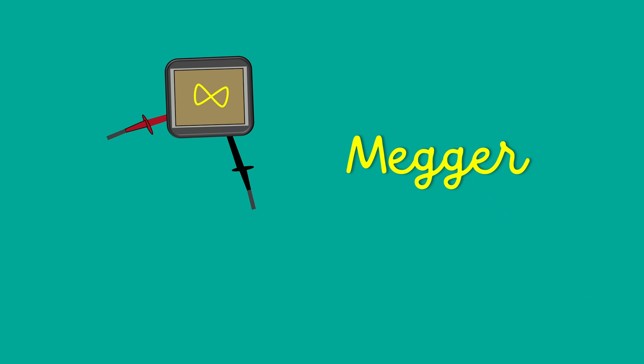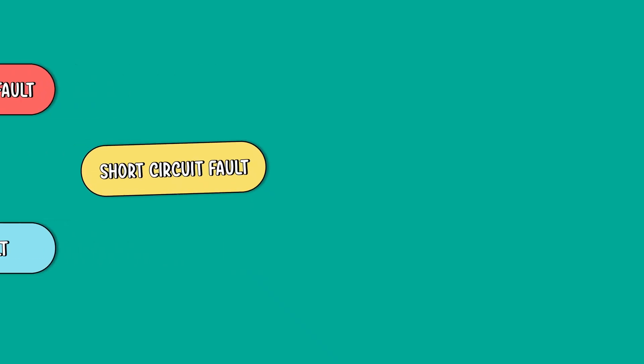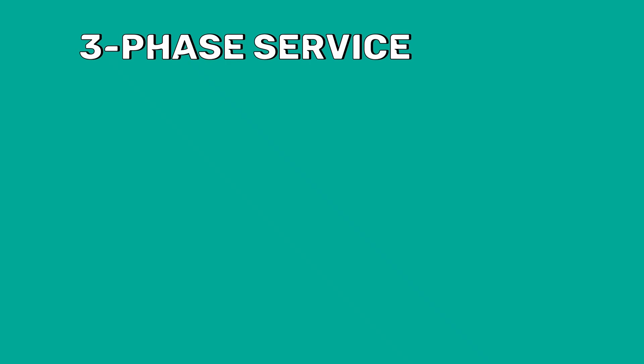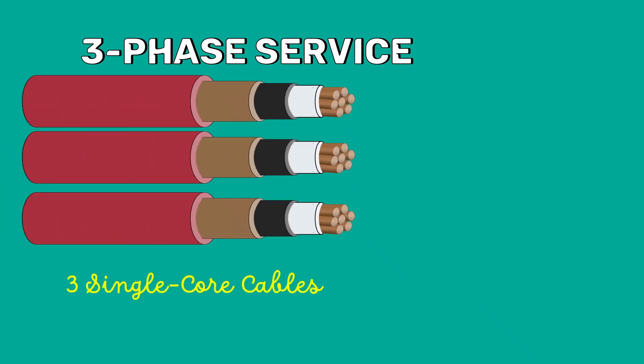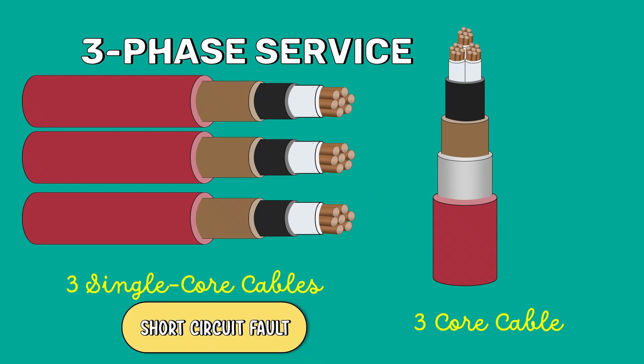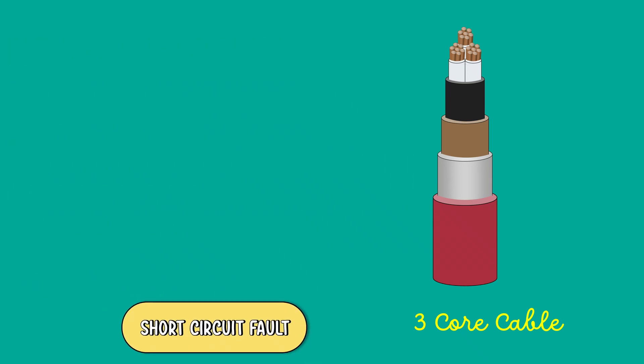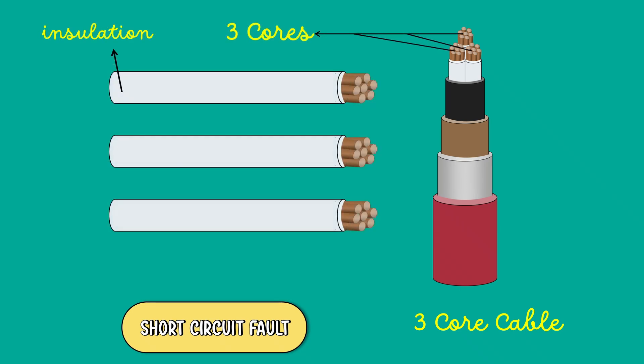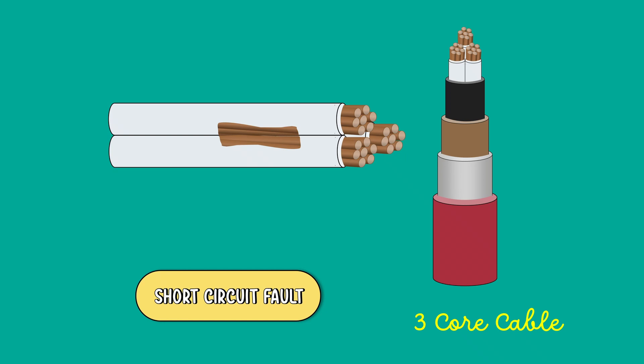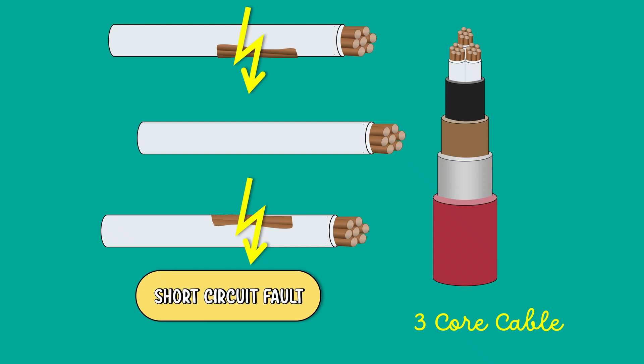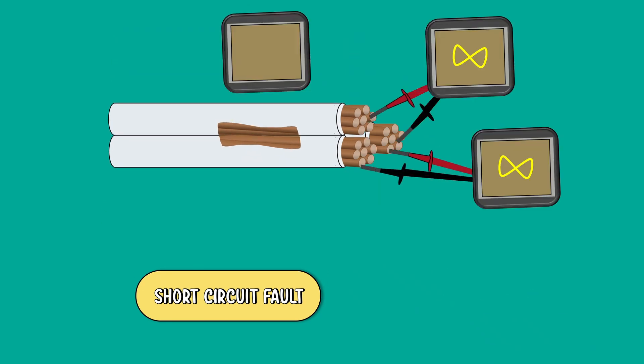Now let's move on to short circuit faults. For a three-phase service, either three single-core cables or three-core cables can be used. This short circuit fault mainly occurs in three-core cables, where the three cores are separately insulated. If insulation failure occurs, these conductors will come in electrical contact with each other — this is the short circuit fault. To find which two conductors are short-circuited, we measure the resistance between the conductors. If the Megger gives a zero reading, it indicates a short circuit fault between those conductors.